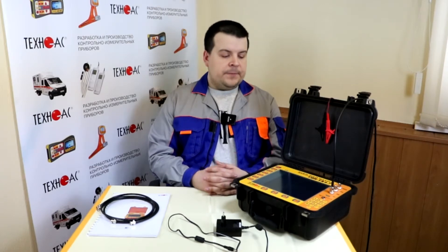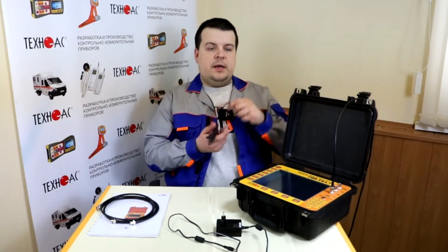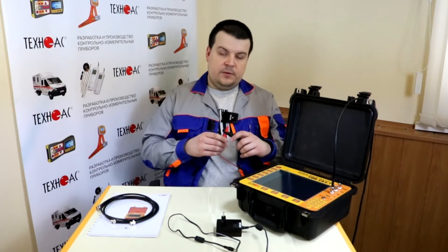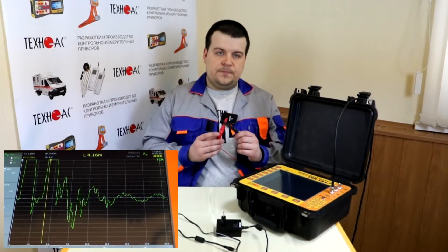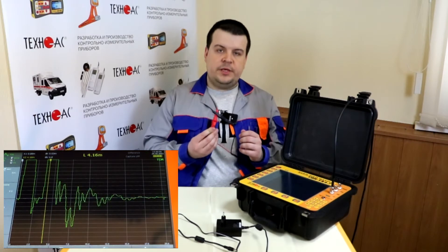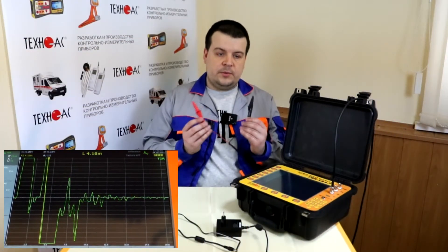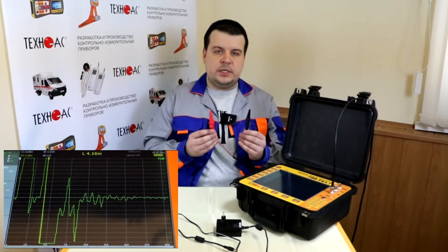Before demonstrating how this device works, I would like to show that you can check it internally. We will connect two leads of the device together. When I connect the leads, the device will indicate a short circuit because the two leads are shorted between each other. When I disconnect the leads, the device will indicate an open circuit — and the same way it will also indicate the fault in the cable.